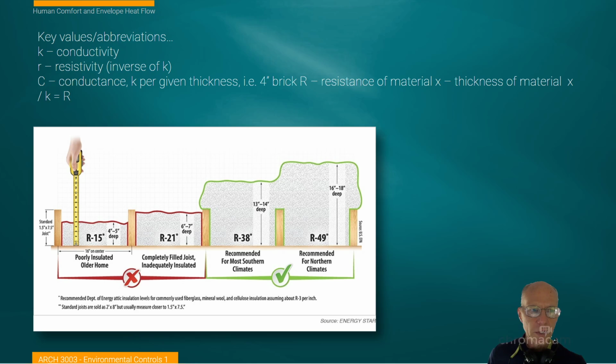So here's a graphic of this idea of R values. In this case, this is probably some type of foam insulation or a fiberglass insulation. And typically they all have a thermal conductivity to them, which when given over a certain thickness of material gives you a certain kind of stacked up resistance in R value. So typically, if you double the thickness of a material, you kind of double its R value. And that's not always a linear calculation.